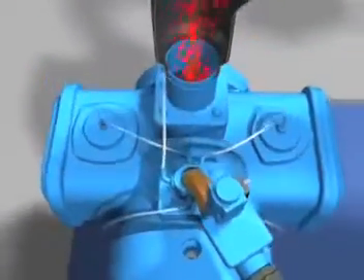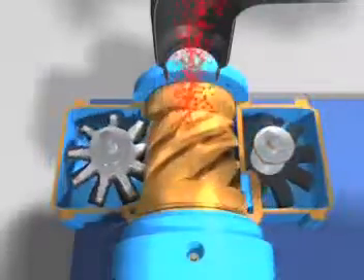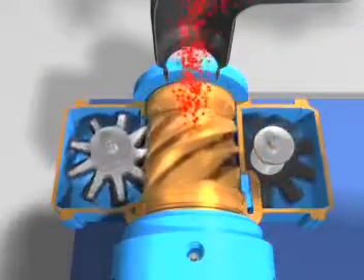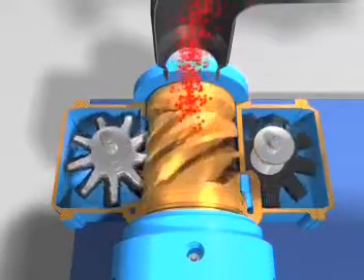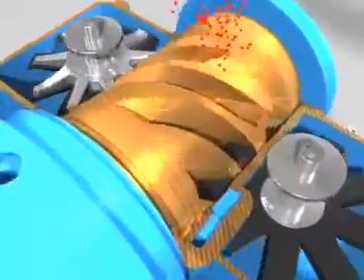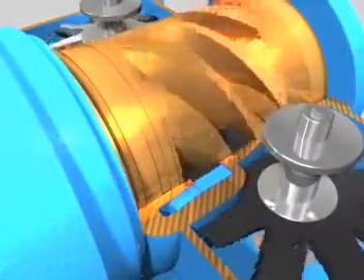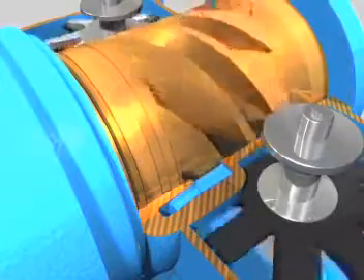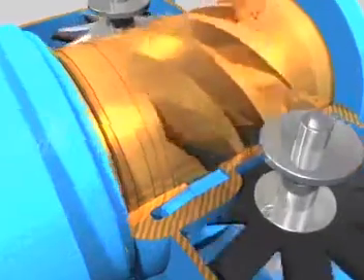The air end consists of a single main rotor and two gate rotors. Atmospheric air enters the compression element and fills the flutes of the main rotor. The gate rotors engage with the flutes and form two compression chambers above and below the main rotor.